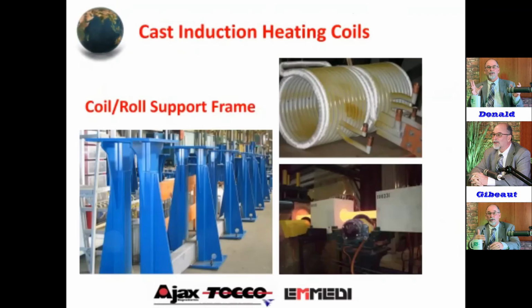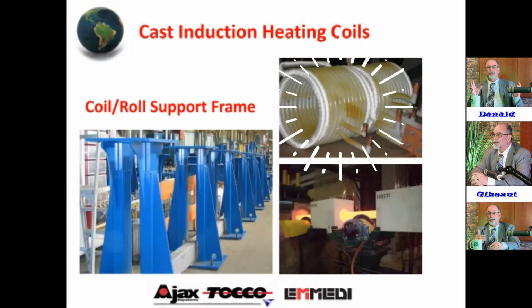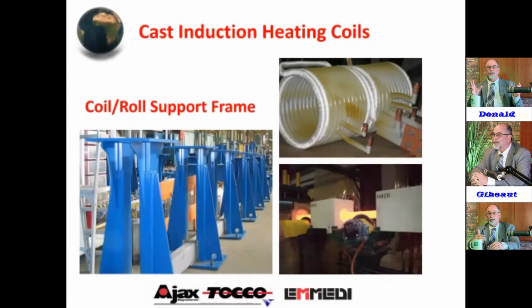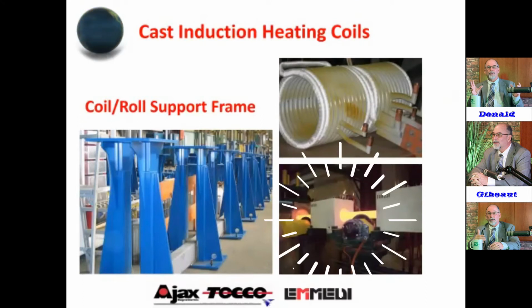So, you get into the induction coils. The upper right is a coil that is encased in refractory, as you see in the lower right, that you've seen on our lines heating. But this is what's inside of there, and it's fluidized bed coated or electrostatically powder coated with a nylon, and then encased in what we call a cast brick coil.